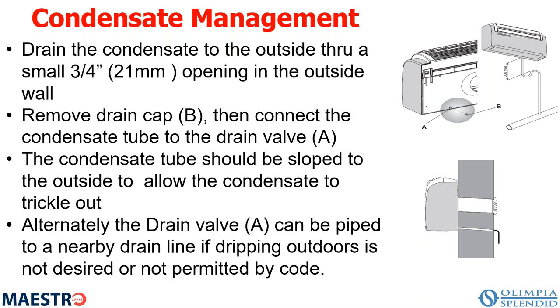Keep in mind that in summer there's almost no condensate. You'll probably never see water come out of this unit in summertime, but that doesn't mean it's not removing water, because it is. The water is allowed to build up and then pumps to the condenser coil, where it basically re-evaporates into the exhaust air. This has been done with room units for many years, but it proves very effective in increasing efficiency while eliminating the need to send a lot of water somewhere.